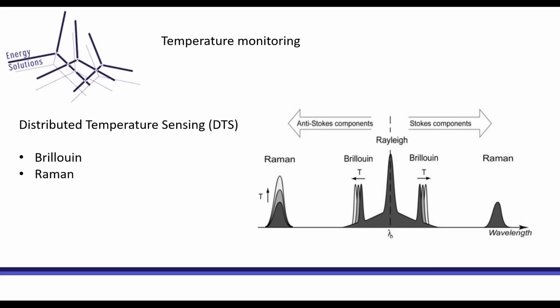The Brillouin technology uses a frequency shift in the signal that is sent, and basically the main difference between the two is that Brillouin is used for longer ranges because it's less influenced by the length. But the Raman system has a limited range because the farther away the pulse goes, the fewer reflections you get.